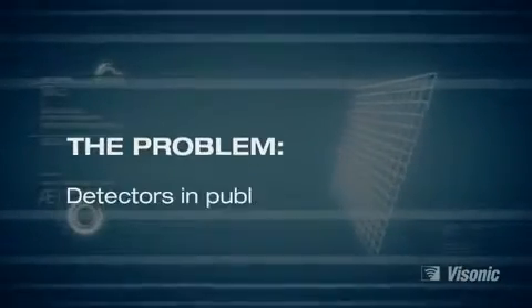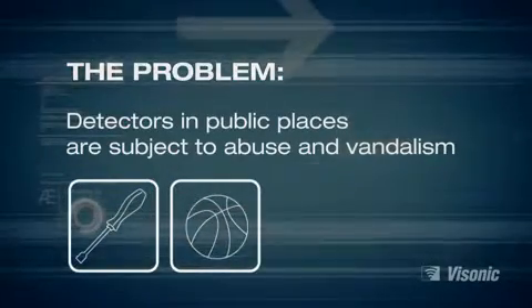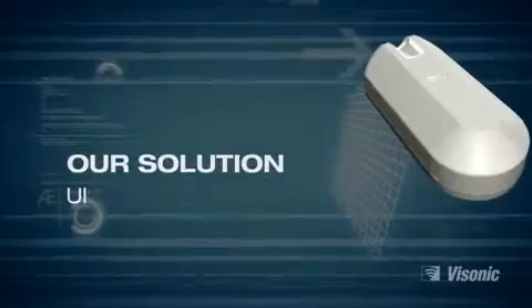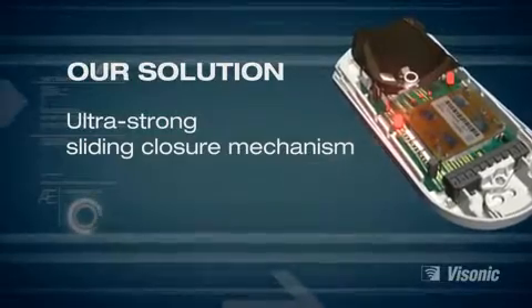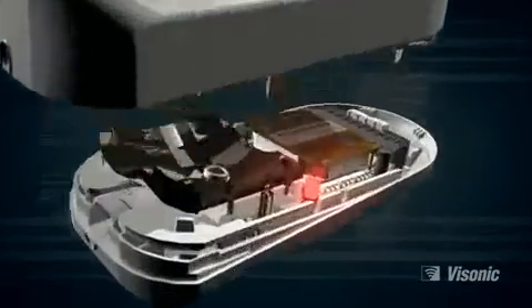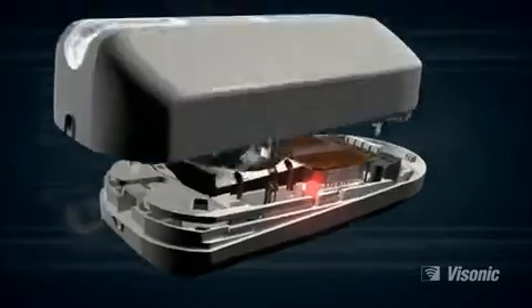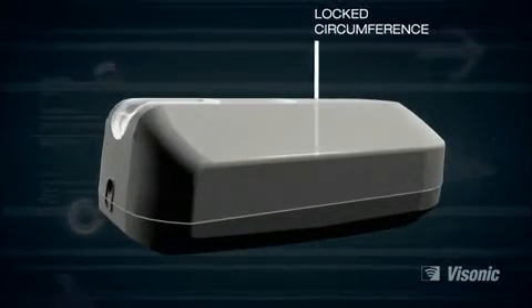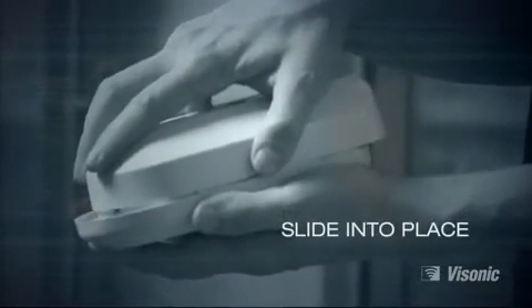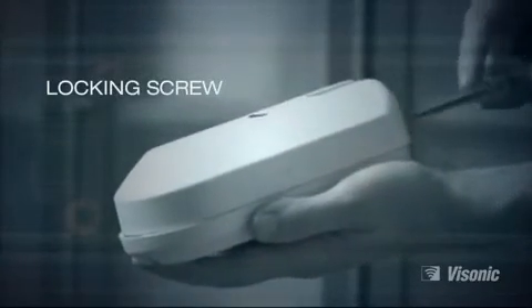The problem. Detectors installed in public places are often subject to abuse and vandalism, sometimes even unintentional. Our solution: in addition to the V-slot anti-vandal optical window, an ultra-strong closing mechanism. A sliding closure mechanism makes tampering impossible — it's not based on a single hinge. It creates a locked closure around the full circumference of the detector. Closing the unit slides the cover into strong grooves within the base, and the screws lock it firmly and almost hermetically into place. The sliding mechanism also makes opening the unit for replacement or maintenance a snap, and all electronic and optical parts are protected by the plastic housing.